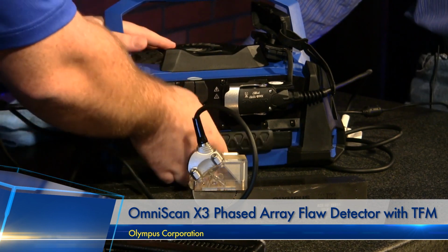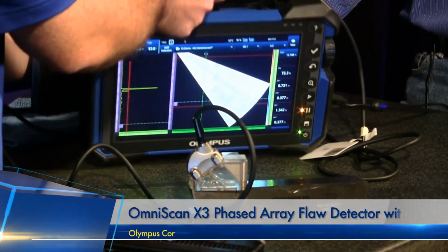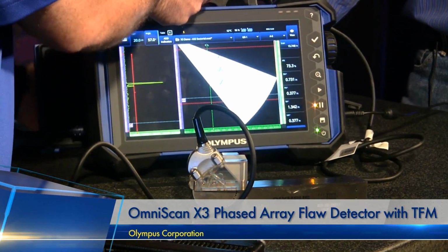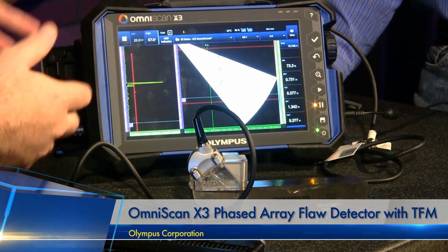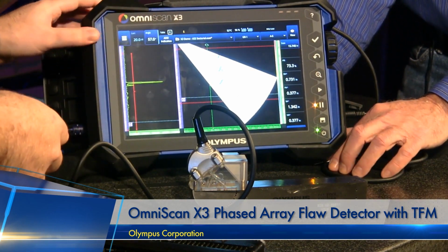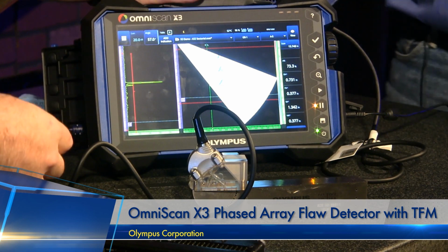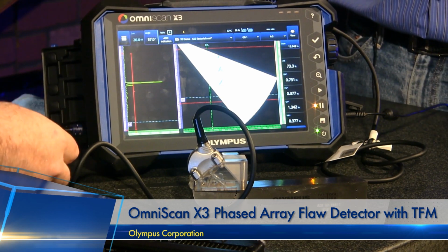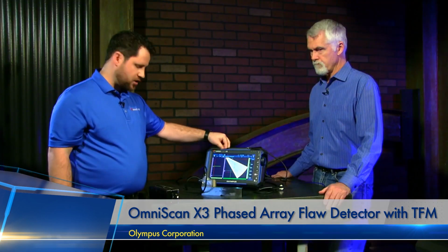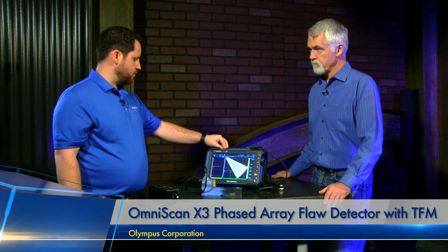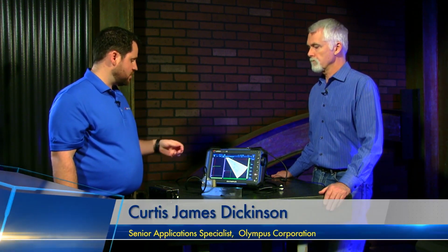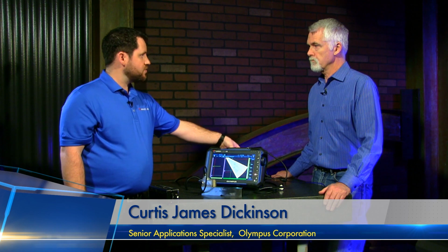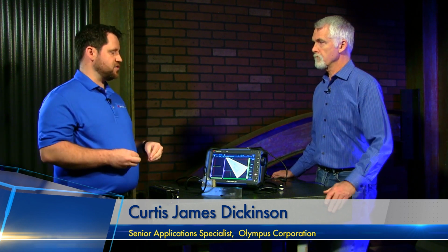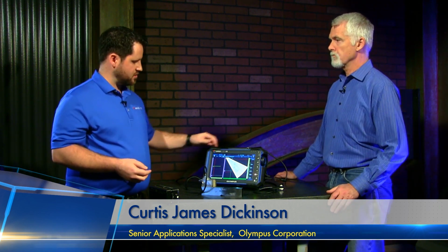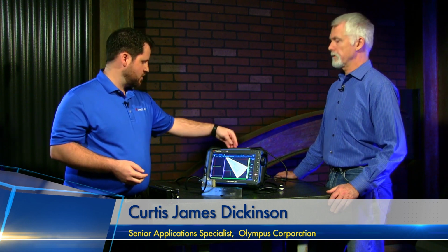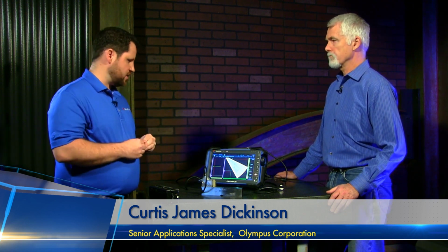Okay. And then with that change came some differences in how you connect and how you get around the unit. On the top side of the unit, we have our typical phased array connection. We have our encoder connector, which is pinned out for 3-axis worth of information. And we've added a second UT channel so that our users that take advantage of TOFD inspections don't have to necessarily steal from our phased array connector. Right. So there's 2 dedicated channels there.